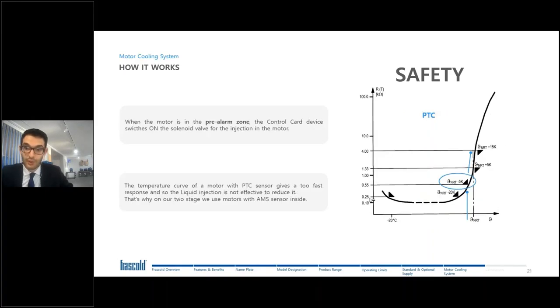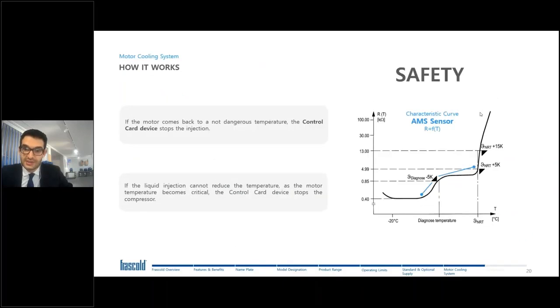But look at the standard PTC that are inside the compressor. In this case, you have the area in which you cannot do anything, and then errors, so alarm and so compressor stopped. In this case, there is no possibility to do something. With our system, instead, we can do something. We can inject only if it's needed, and in this way we prevent stopping of the compressor, which obviously can always create problems for the final system, the final user.